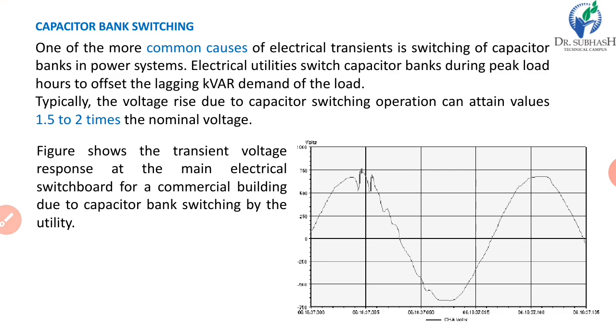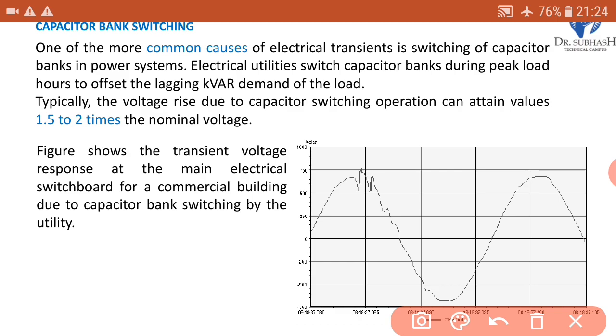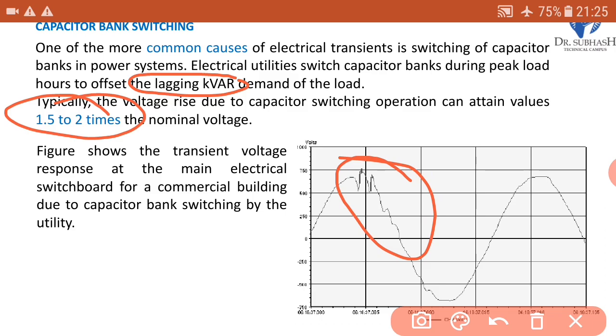Now, capacitor bank switching. One of the more common causes of electrical transients is switching of capacitor banks in power systems. Electrical utilities switch capacitor banks during peak load hours to offset the lagging kVAR demand of the load. Typically, the voltage rise due to the capacitor switching operation can attain values of 1.5 to 2 times the nominal voltage. So due to this, a transient may be generated. This figure shows the transient voltage response at the main electrical switchboard of a commercial building due to capacitor bank switching by the utility. So here we can observe the effect of capacitor switching, and due to this the transient voltage is generated.